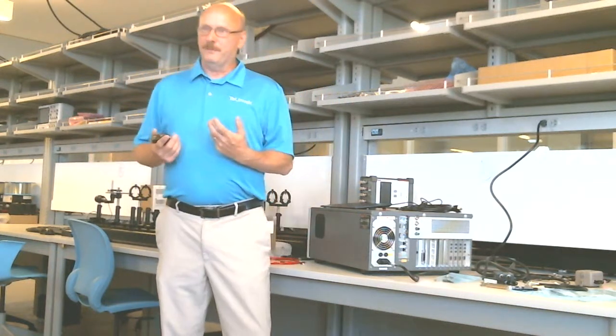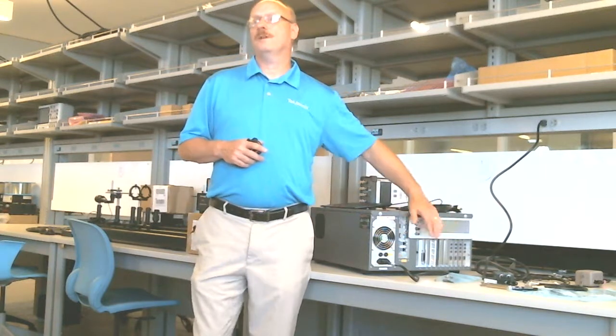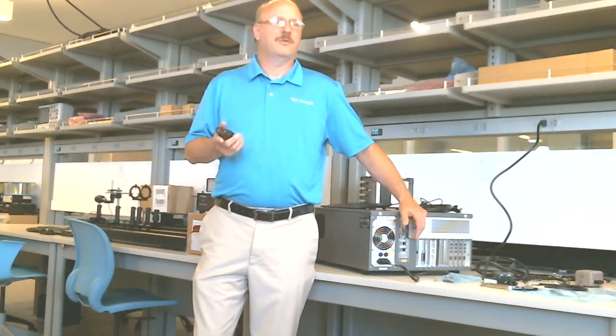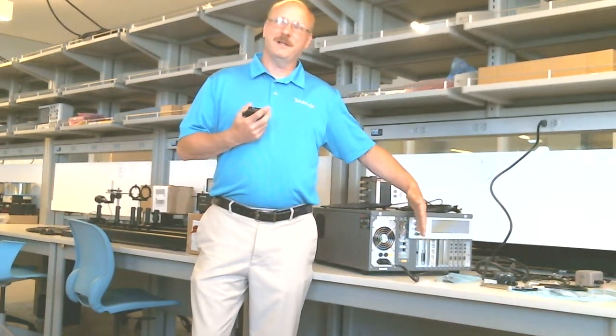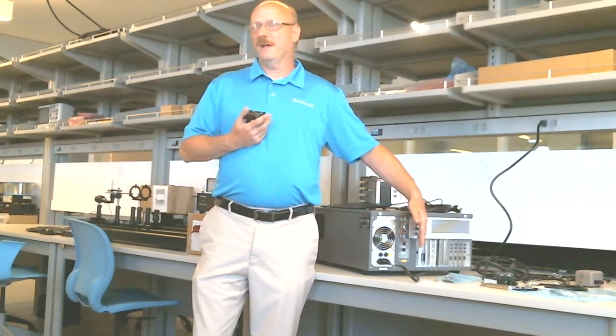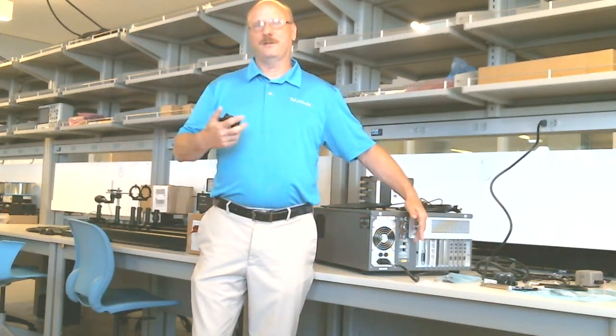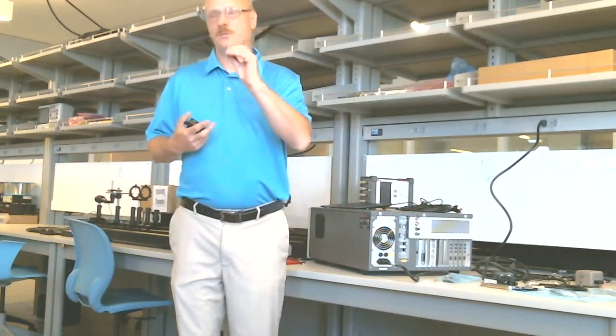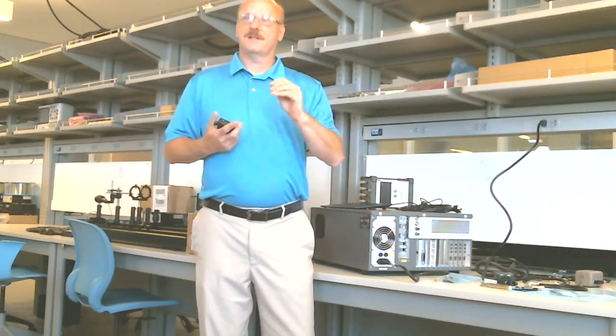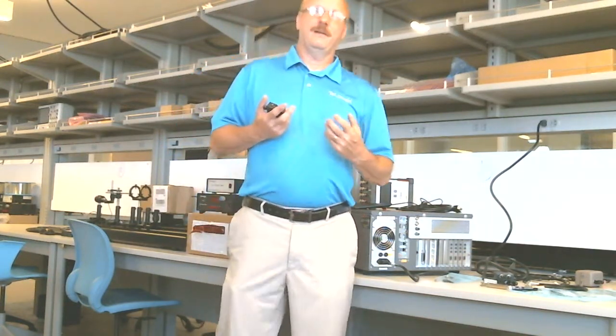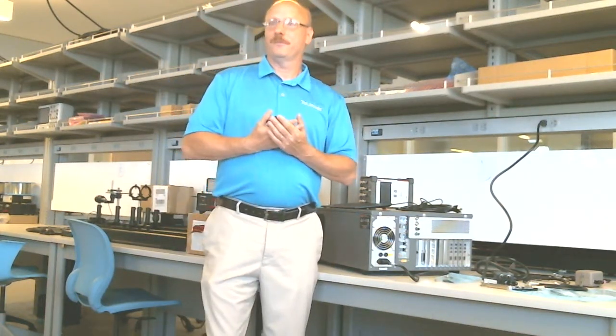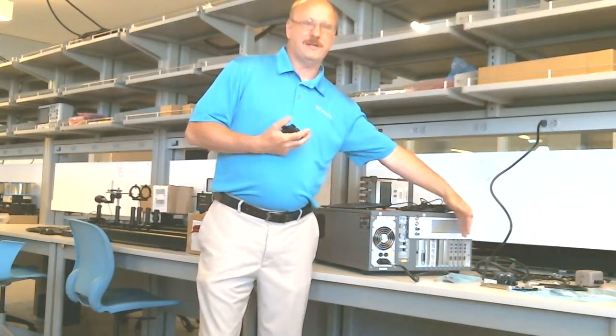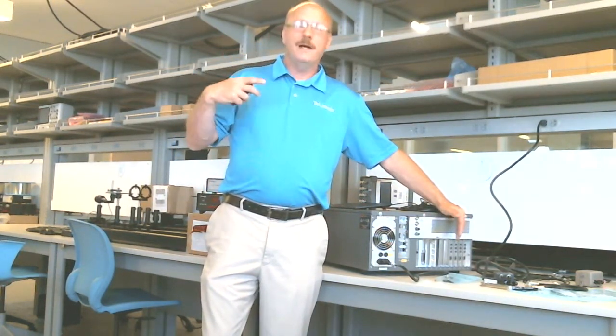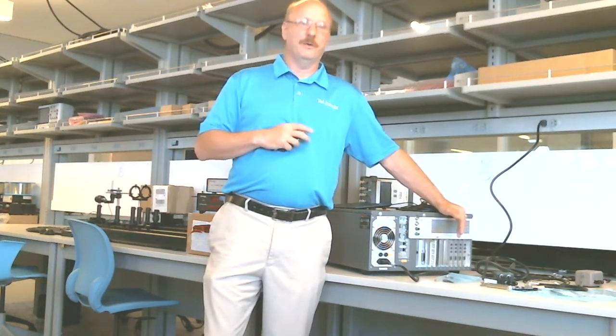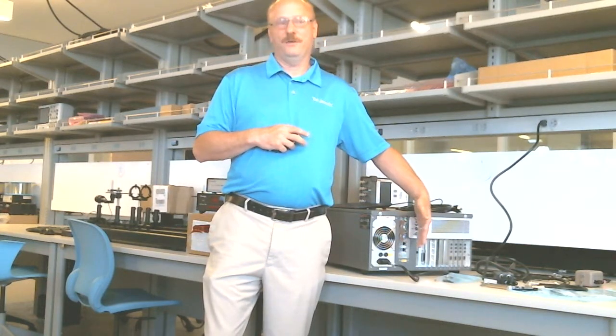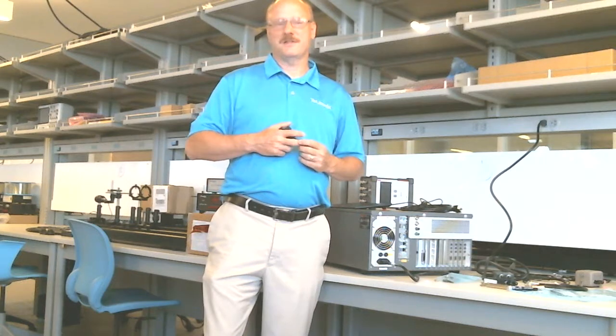Here's the catch: if I were you guys, forget it's even there, because you've got 4 SMUs. An SMU is going to be a better choice for making ground than the ground unit, which sounds weird, but the reason is this ground unit doesn't have ranges, it's just fixed. The best way to get a good ground is to switch to the lowest range possible and source 0 volts, because your error is range dependent, the higher the range, the more error you'll have on that voltage source. The SMU has ranges, so you can range it down to the nanovolt range and source 0 volts, and you'll get a real accurate ground. This ground unit can't do that, so if you have an SMU, use it, because it's going to give you a better ground.